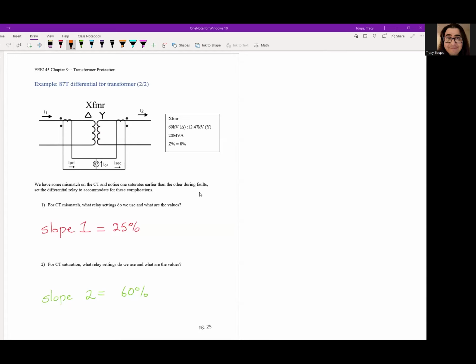Okay. So slope 1 is for lower values of current for CT mismatch. Slope 2 is for higher currents where it'll go into fault current territory and you'll have to overcome a 60% restraint to have the 87 relay operate for a faulted event. But remember that an internal fault will always have a very high percentage here. Typically internal faults are like 200%, 300%, 400%. It's really high, so you should not have any problems with an internal fault. It's an external fault where you want to make sure that your CT saturation does not trip your transformer for a fault somewhere else. And that's why we need the 60% to make sure that CT saturation doesn't trick the relay into thinking an external fault is actually an internal fault, and the relay will just basically misoperate.